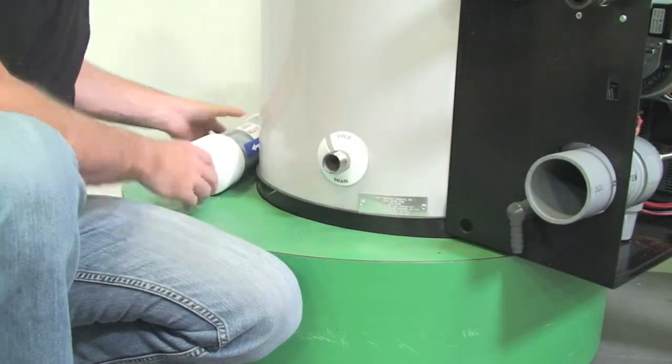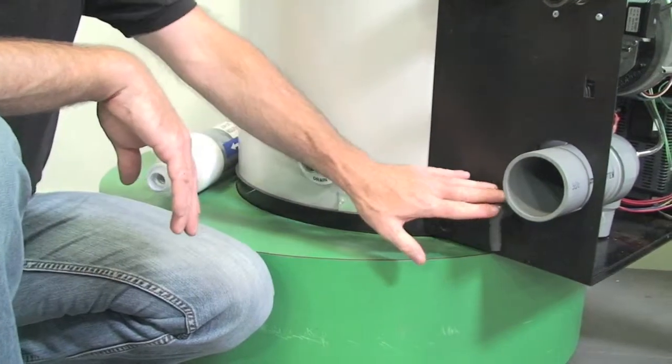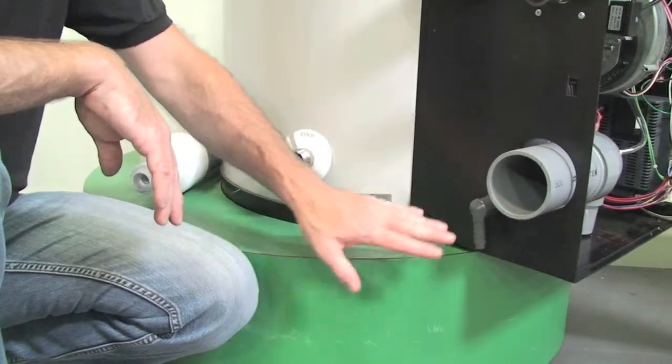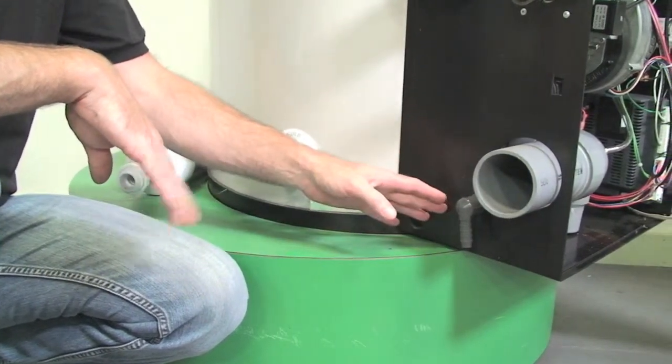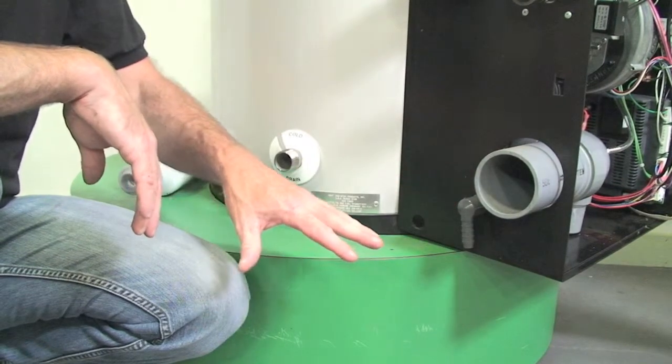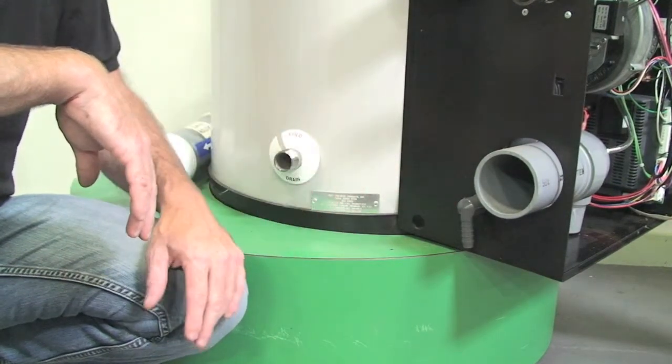The other thing that we want to pay attention to on the condensate is we want it to drain away from the unit. We do not want it to drain back, so we recommend about a quarter inch per foot draining away into either our floor drain or into a condensate pump.